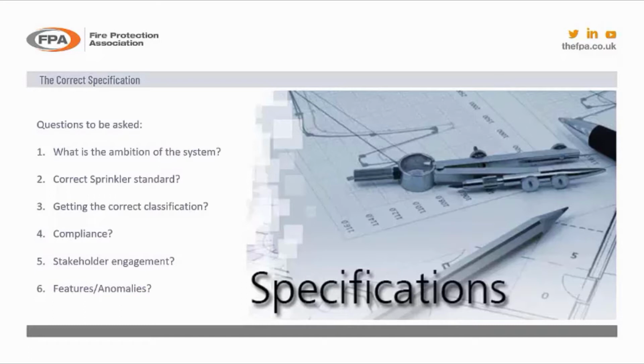What is required of the sprinkler system? What standard is the sprinkler system to? Is it classified correctly? Have they taken into account the full height of the building? Have they taken into account who's involved? What stakeholders are involved? Does it need to comply? And are there any features or anomalies that may affect the specification or any part of the sprinkler system, which then may mean it does not comply? And these are key issues that need to be resolved early doors in the specification with key stakeholders to ensure that the specification is up to date.